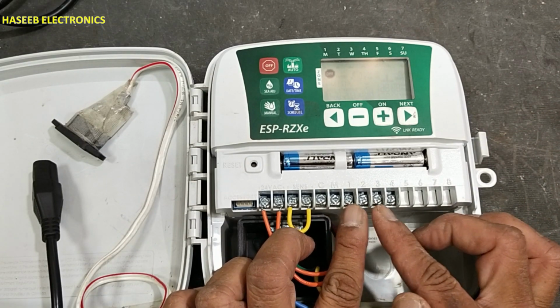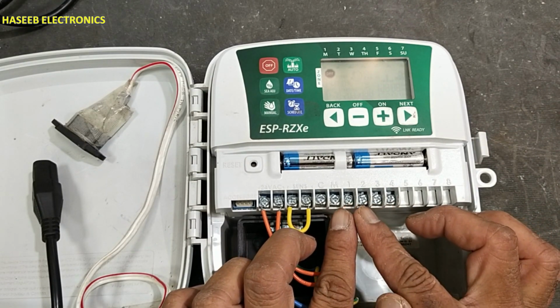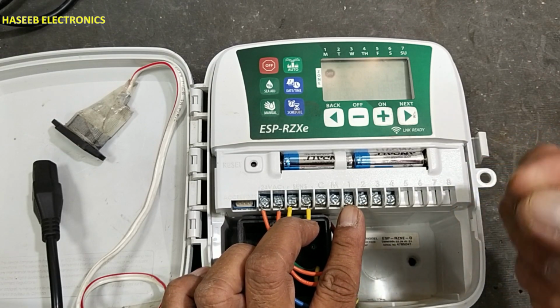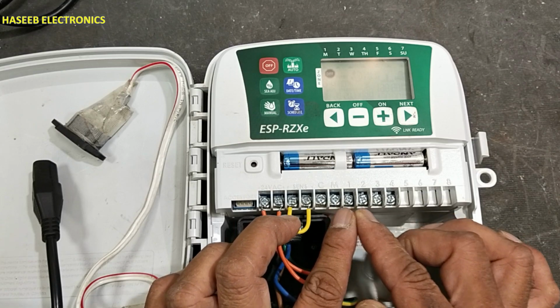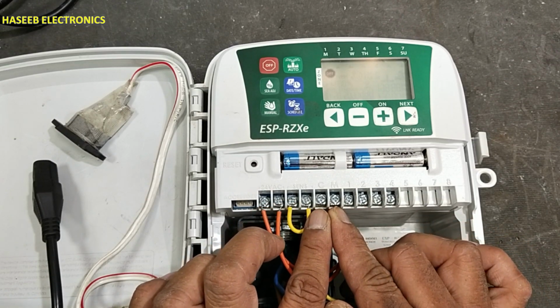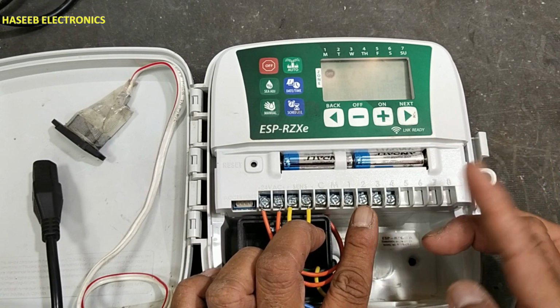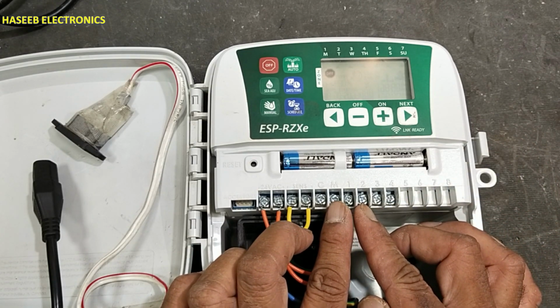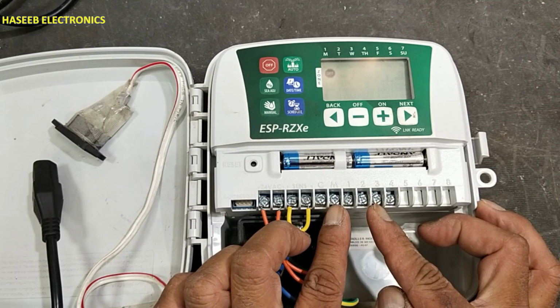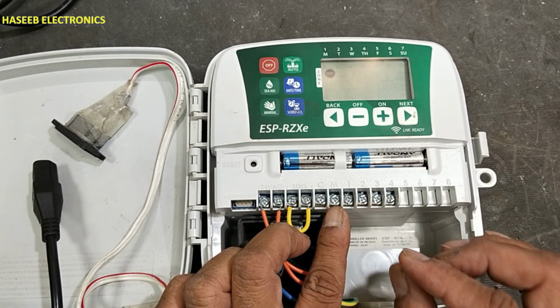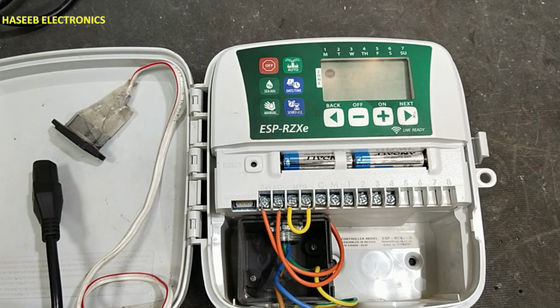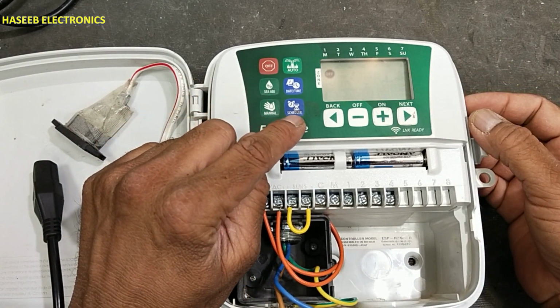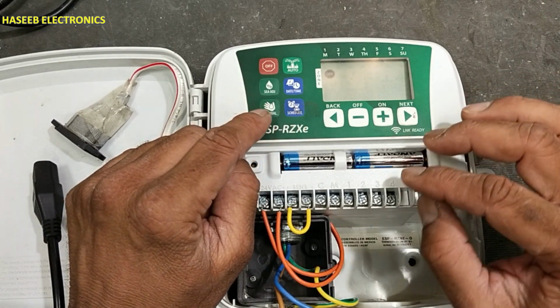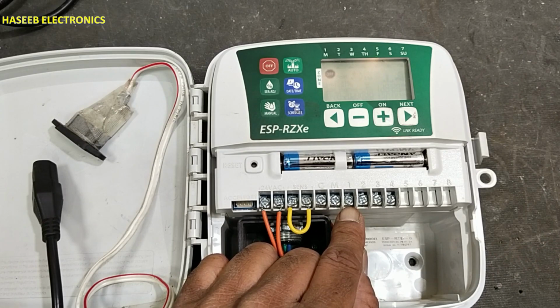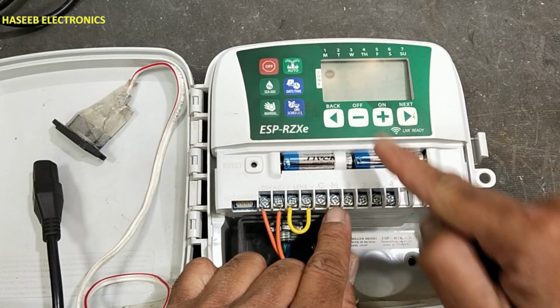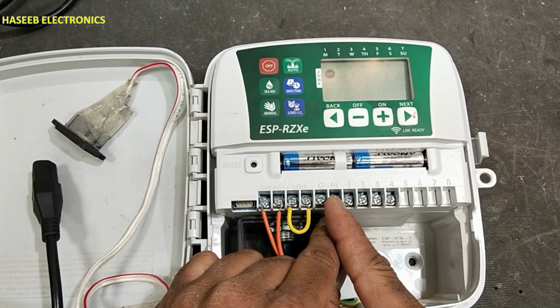Whenever we select any channel, any area, any station, for example channel number 1, at that time channel number 1 plus the master valve will turn on. If we select number 2, then 2 and the master valve. Sprinkler number 3 with the master valve. So the master valve will turn on with each station. Whenever we program a schedule or program manually, for example turning on channel number 1 in manual or auto mode, it will turn on 1 and the master valve.